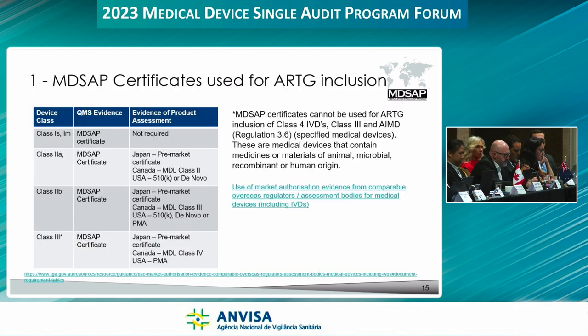MDSAP certificates can be used for all classes of devices except for class three devices that contain specified materials - medicines, materials of animal, microbial, recombinant or human origin. For those devices, we only accept a TGA or a European certificate. So the class of device determines the requirements. For class 1S and 1M devices, an MDSAP certificate alone can be used to include those products on the register.